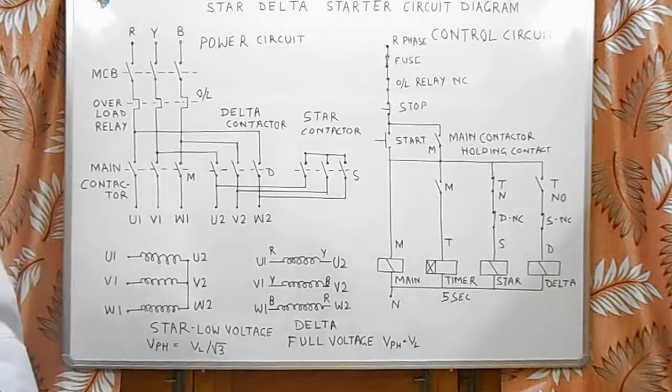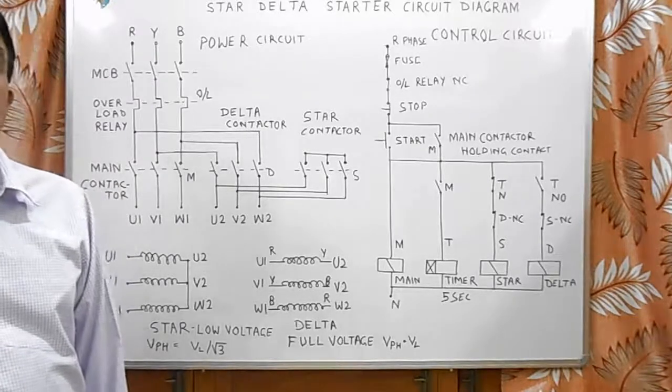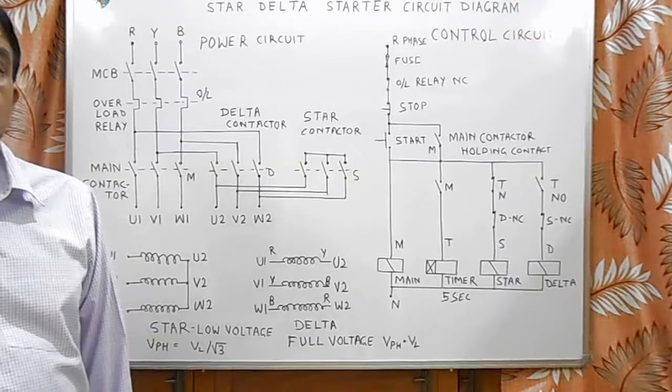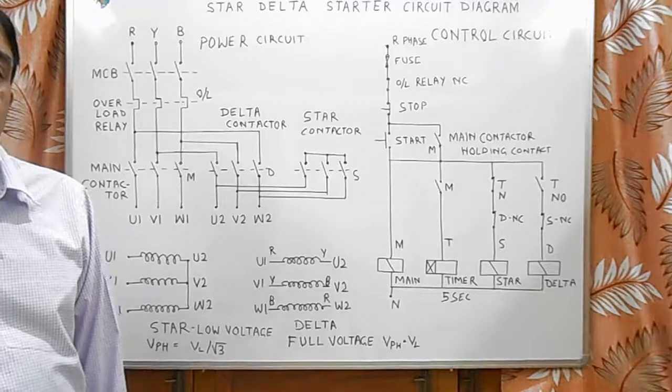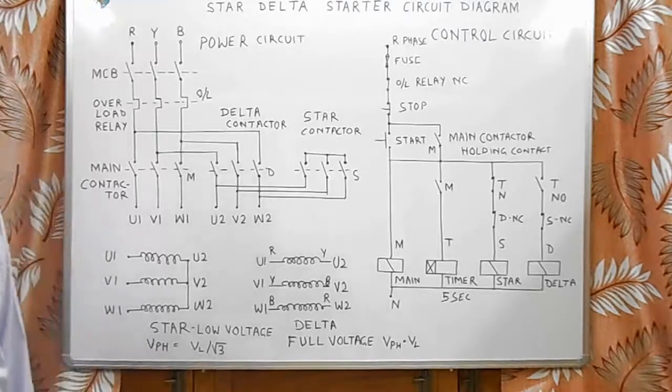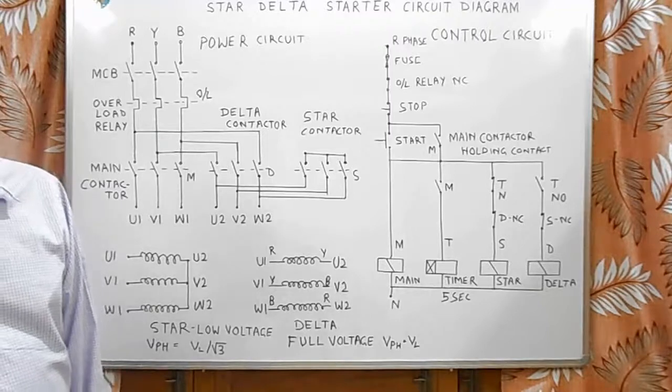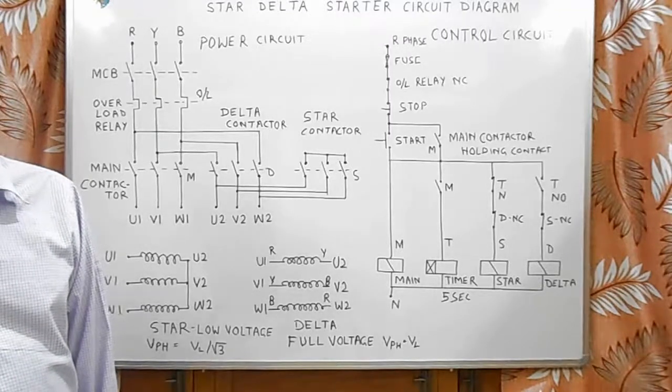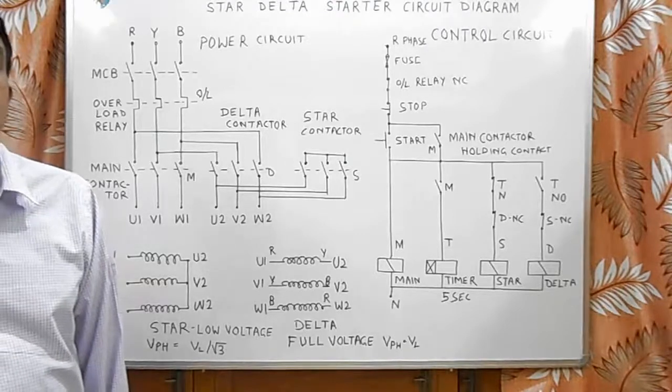I think this circuit is very clear to you. Basic concept of star-delta starter is to start motor with reduced voltage and then run at normal supply voltage. This scheme is suitable for starting motor at no load, but if there is continuous load, this scheme may fail because starting torque at low voltage is very less.